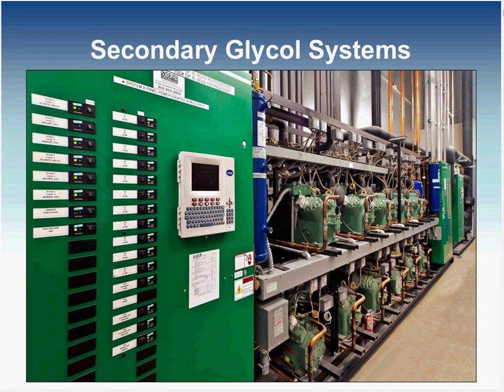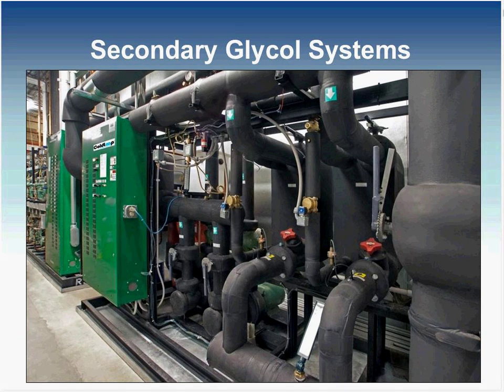The second part of it, the secondary loop, would be a typically 35% propylene glycol system that's used as a cooling fluid. The fluid is cooled in the back of the room, and there are some pumps that send it out. So you have a rack on one side of this hallway, and at the other end of the hallway you have the pump skid. In the pump skid, there are some chillers. Let me see if I can get a pointer tool. The chillers are back here. So the refrigeration system is connected over to the chillers, and it's cooling the glycol. The glycol is being pumped through the store with the pumps back here. The pumps take the glycol and pump it through the chiller. It gets nice and cold. The cold glycol goes out to the store, goes through the cases, cools the air, comes back warm, comes back through the chillers, and is cooled again. So you have a continuous cycle.